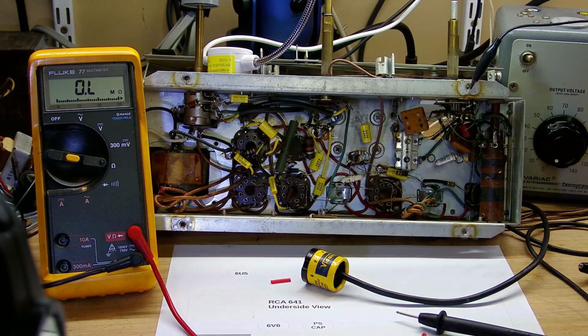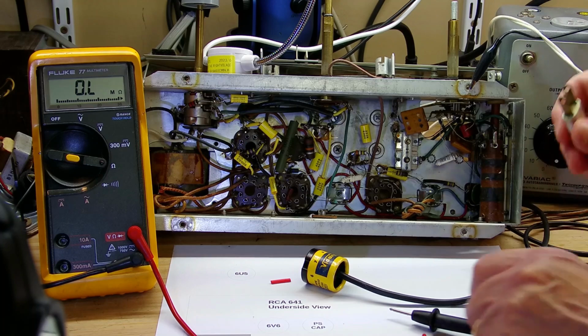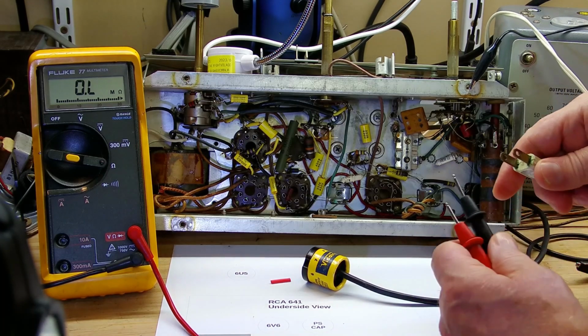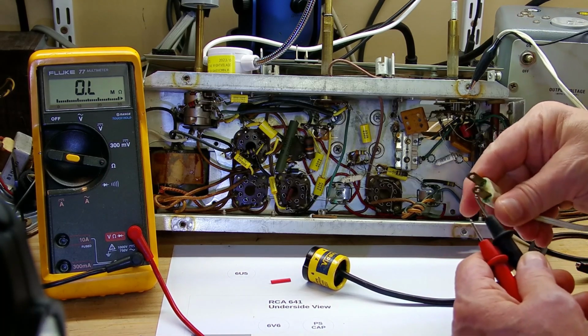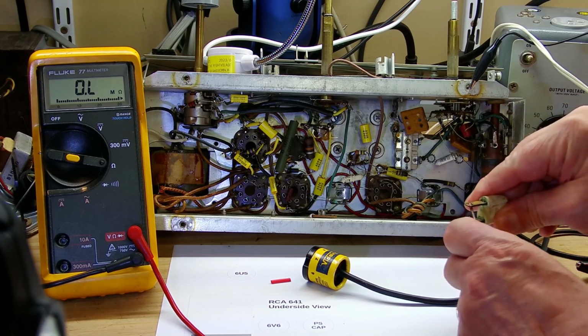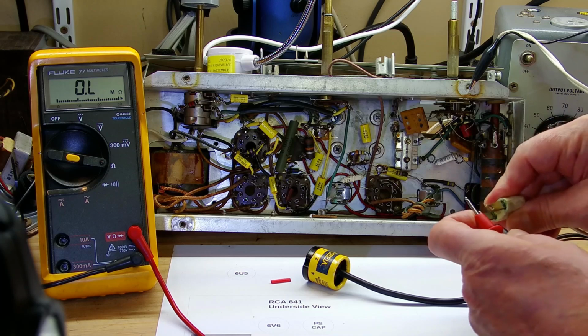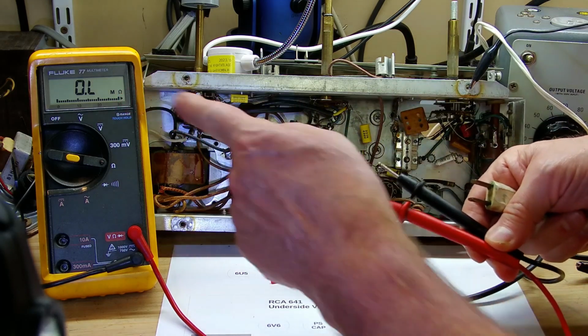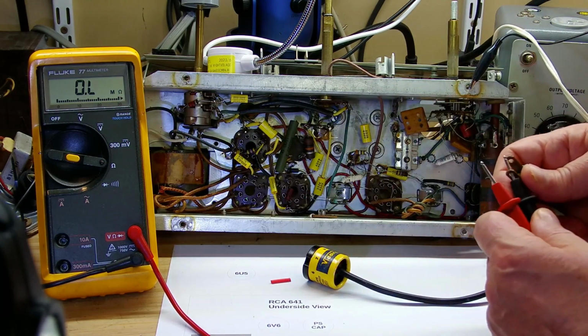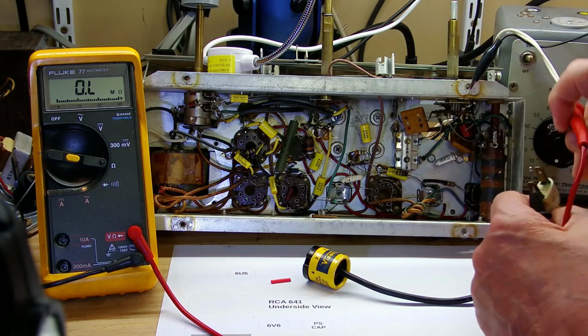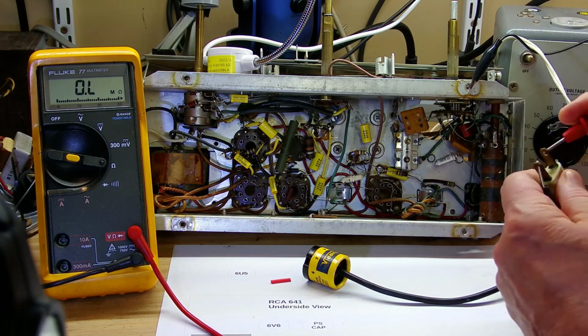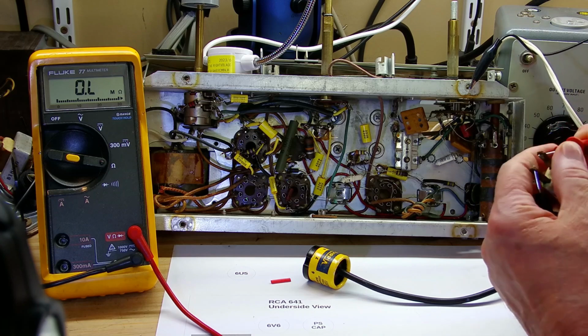The first place we're going to start is the AC line input. I'm going to put a resistance measuring device, my ohm meter, right here, and check the resistance across the primary winding of the transformer.